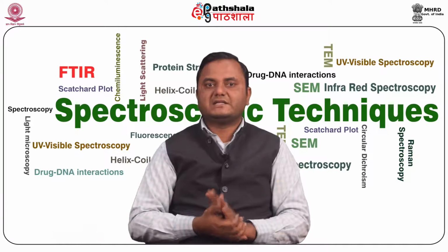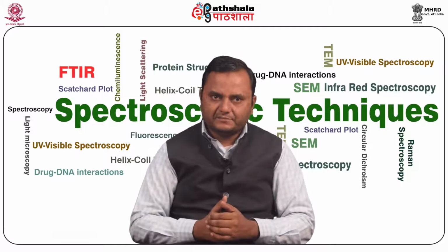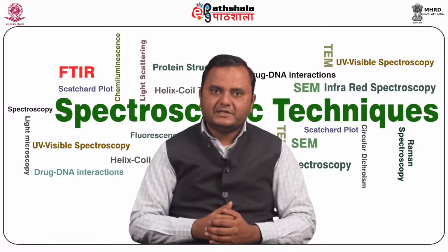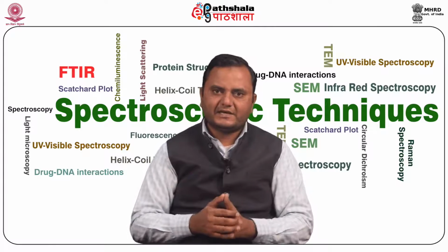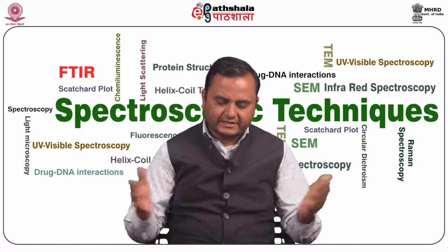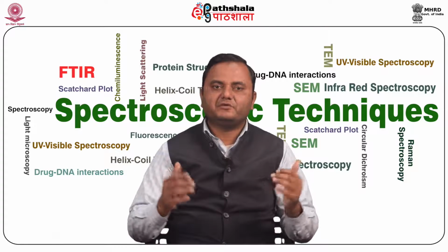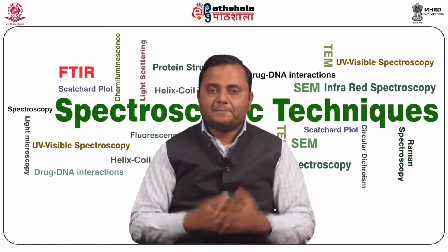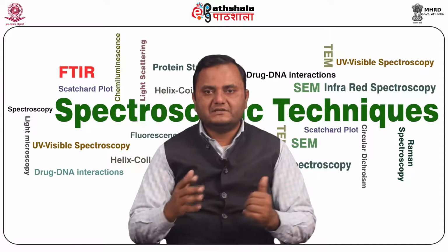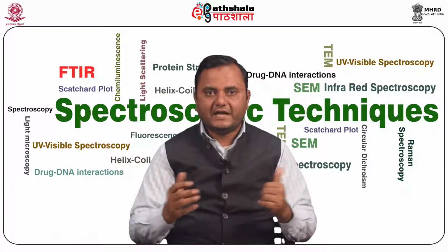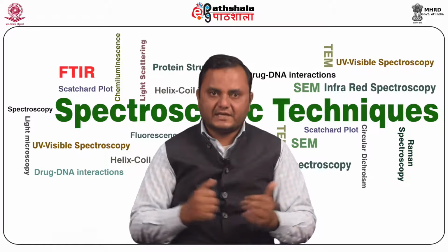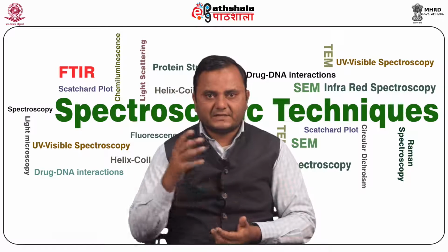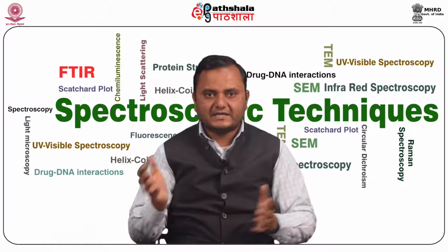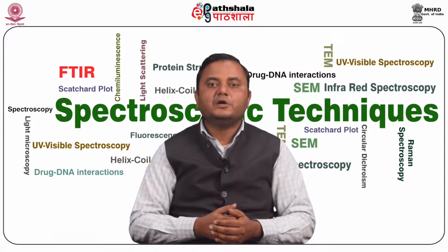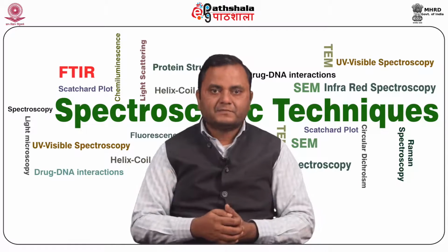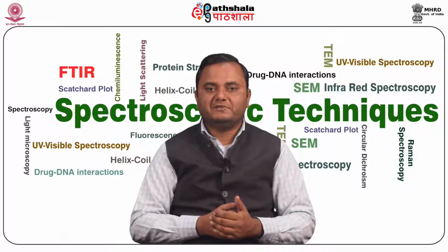Now we talk about sample handling. Sample handling is a very essential component of IR spectroscopy. If you are unable to handle the sample properly, there are many chances of error, so you have to be aware of sample handling. It is frequently the most difficult and time-consuming part of IR spectrometric analysis, especially for gases. The spectrum of a low-boiling liquid or gas can be obtained by permitting the sample to expand into an evacuated cylindrical cell equipped with suitable windows.